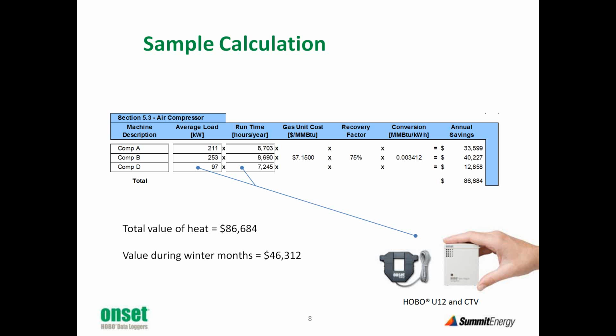Now, as I mentioned, the key is to get the facts. It's one thing to simply look at the compressor and make the observation that there's heat and we ought to use it. The question is exactly how much heat is there and what's it worth. So the recommendation is to get the facts and do the analysis. This is an example where we've used one of Onset's HOBO devices on each of 3 air compressors in my example in order to determine the average load in kilowatts and also the run time for a year.